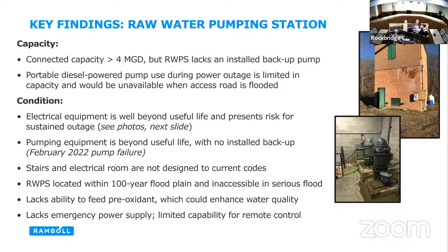And so right now we have current agreements with our customers, the city and the PSA, that half of the capacity goes to each of those 2 customers, whether it's wastewater or water. And so the expectation is there's 4 million gallons a day capacity. But the way it's currently set up, I think what we're saying is that there's not 4 million gallons a day capacity. And the health department is pushing us to derate the capacity to 2 million gallons a day based on the fact that we aren't meeting the redundancy requirements.